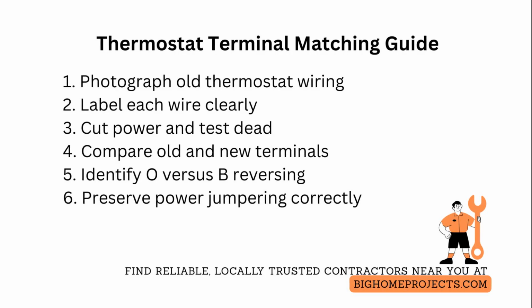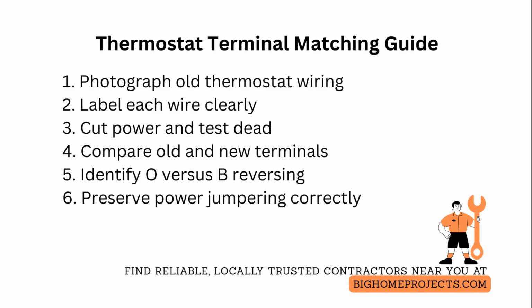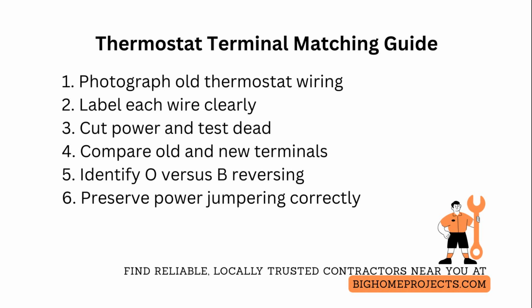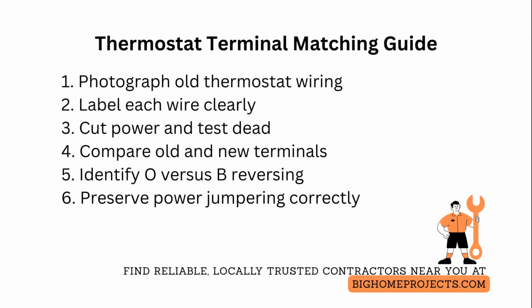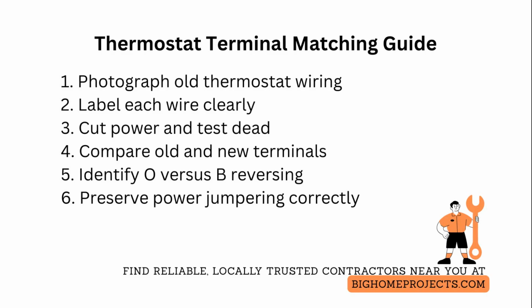Back to the control board terminals and confirm that letters like W, Y, G, R, C, and O, B correspond to the exact terminal functions on the equipment, not just the thermostat. When dealing with heat pump systems, identify whether the system uses an O or a B reversing valve signal and whether it is energized in cooling or heating. Swapping those two will reverse system behavior.